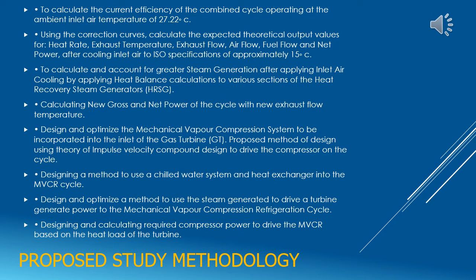The proposed study methodology for this project is as follows. To calculate the current efficiency of the combined cycle operating at ambient temperature, to apply the correction curves and calculate the expected theoretical output values when inlet air cooling is obtained, to account and calculate for the greatest steam generation after applying inlet air cooling by applying heat balance calculations to sections of the HRSG. The new gross and net power of the cycle will need to be calculated to account for the new exhaust flow temperature.